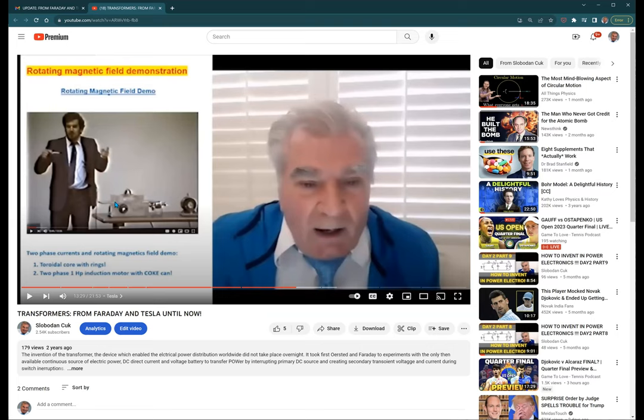So anyway, this contraption below, which I have, is to generate for this two-phase winding of the structure, which is actually really four windings on one side, one phase, and two windings on the other side, and therefore generate a rotating magnetic field. But this rotating magnetic field operates on the leakage of this transformer, not on the main flux.